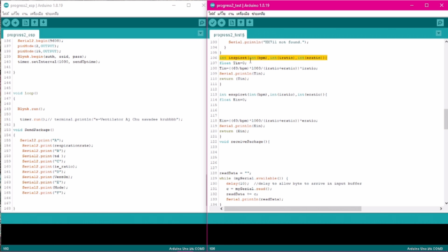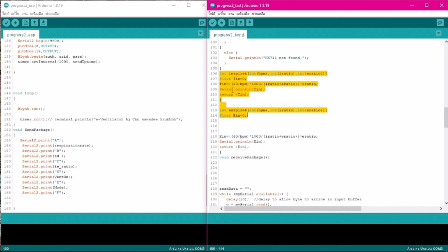And here, this is the function that we use to calculate the inspire time and expire time. The inspire time and expire time use the respiration rate and the IE ratio. So these three values will affect the inspire time and expire time by using this equation to calculate T in and T ex. So yeah, as I mentioned before, if we have more E ratio, the ventilator will also be slower because the expire time will be higher.